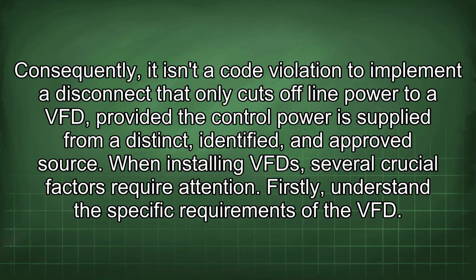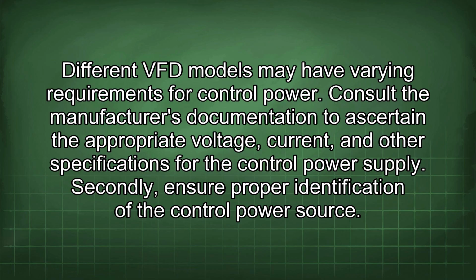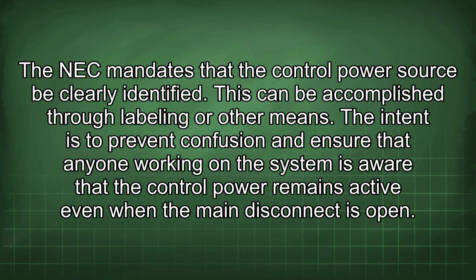When installing a VFD, several crucial factors require attention. Firstly, understand the specific requirements of the VFD. Different VFD models may have varying requirements for control power. Consult the manufacturer's documentation to ascertain the appropriate voltage, current, and other specifications for the control power supply. Secondly, ensure proper identification of the control power source. The NEC mandates that the control power source be clearly identified. This can be accomplished through labeling or other means. The intent is to prevent confusion and ensure that anyone working on the system is aware that the control power remains active even when the main disconnect is open.